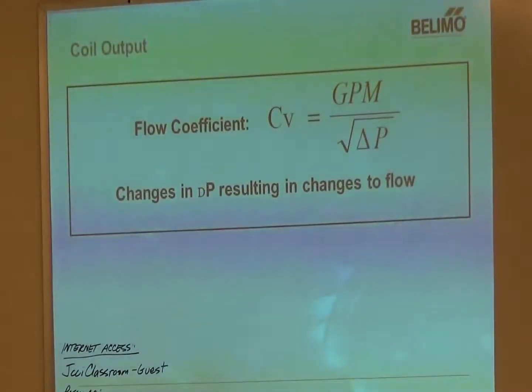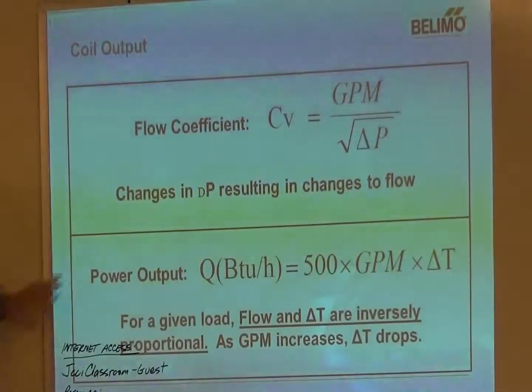And then our power output, the main thing to get out of here is just to be aware that flow and delta T are inversely proportional. So as your flow increases, your delta T is going to decrease, and that's going to lead to that low delta T syndrome that you hear about.